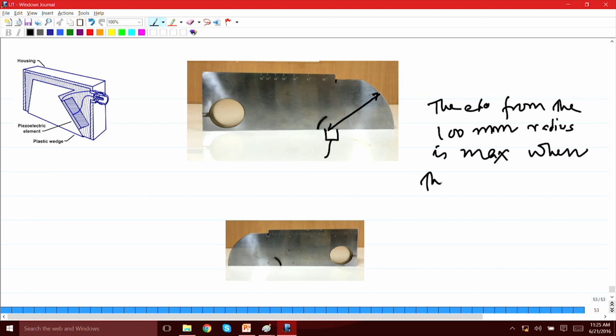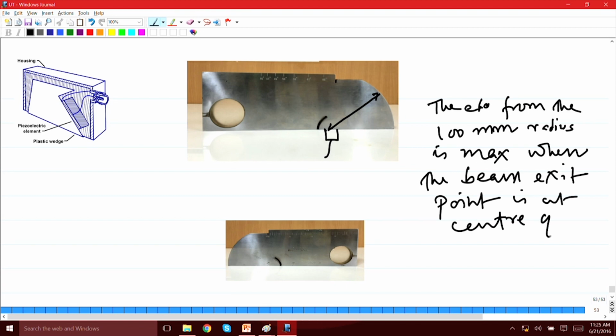So, when the beam exit point is at the center of this curvature, you get a maximum signal. So, what do you do? You take this probe and then move it on either side like this till you get a maximum signal. Okay. So, the moment you get the maximum signal, you stop there and you mark that point.